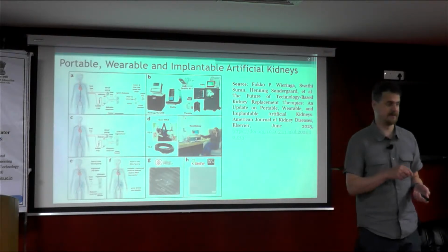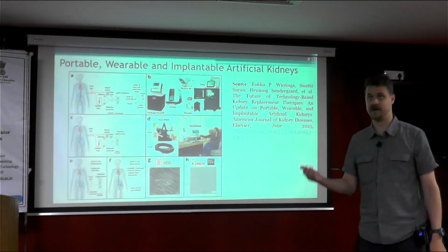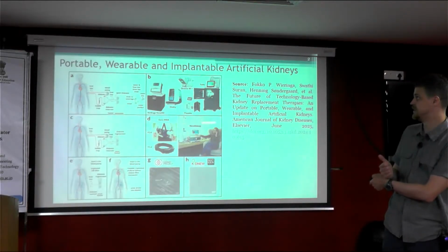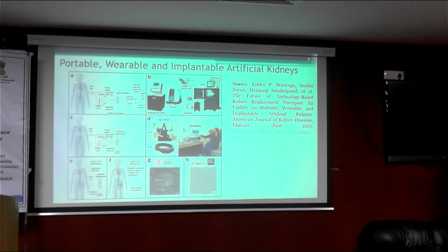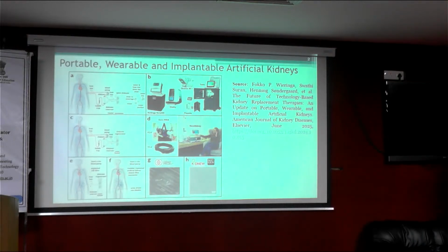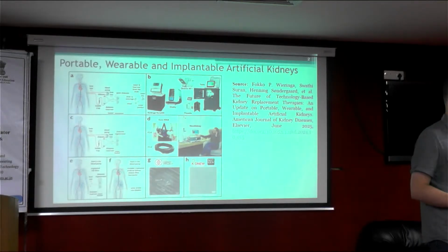And at the same time, if we want to prepare a sufficient volume of dialysis fluid that can be used for one patient, it will require an even bigger volume of water that we have to prepare. So in order to perform this particular procedure safely for the patient, we need to establish a water preparation system or water preparation unit specifically to perform this procedure at home, or at the very least we need to supply the patient with a prepared amount of the dialysis fluid to perform this procedure.